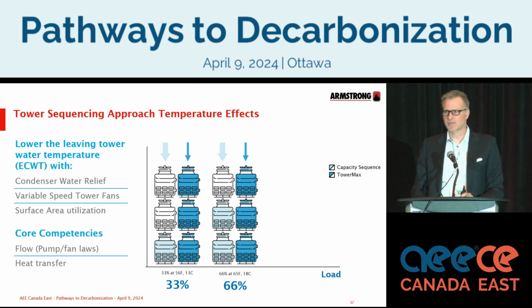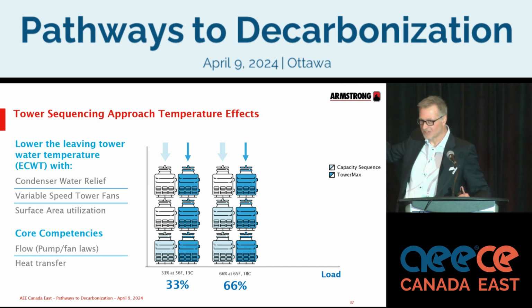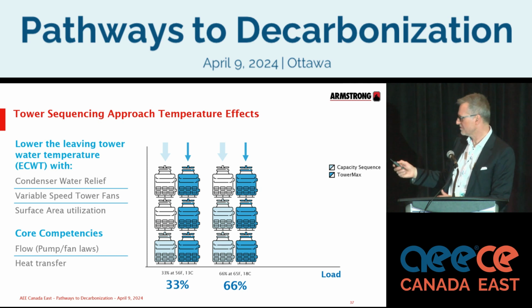When the control logic was off, the plant was running at 0.94 kilowatts per ton. They had 1 fan running at around 90% of speed, and the condenser water pump running at about 60%. When they turned the logic on, the 3 fans were engaged, but the fans were operating at 60% of speed, and the pump speed went up to 90%. But the plant went from 0.94 down to 0.83 kilowatts per ton in 5 minutes. And it was the ability to sequence the equipment.